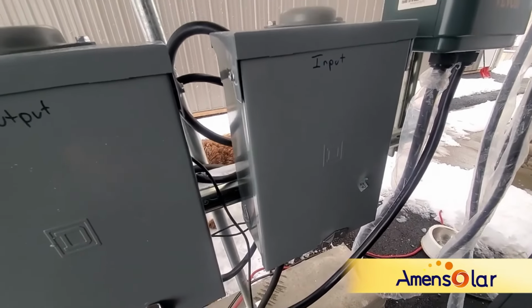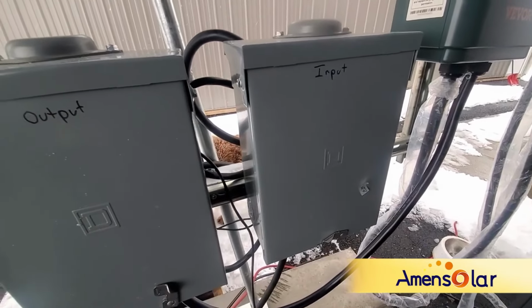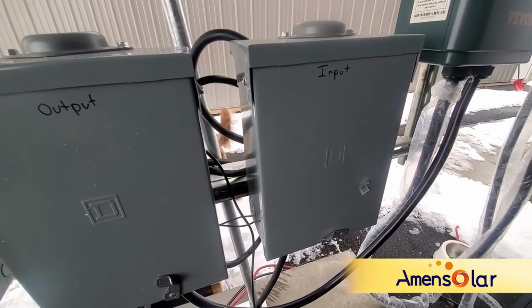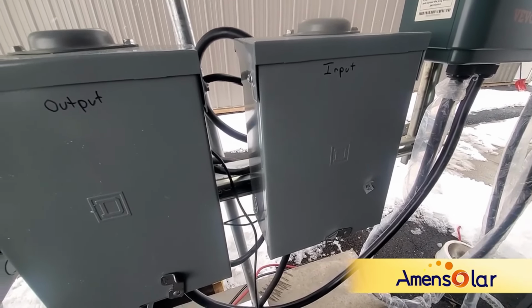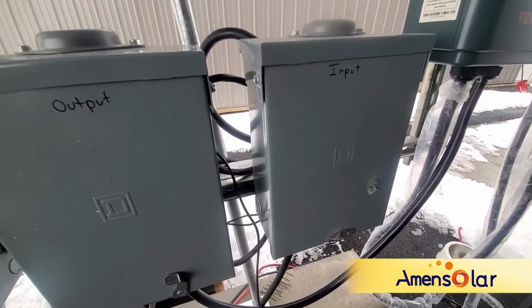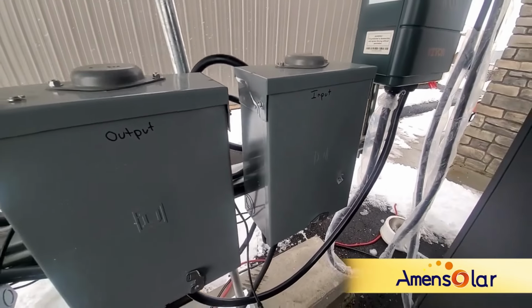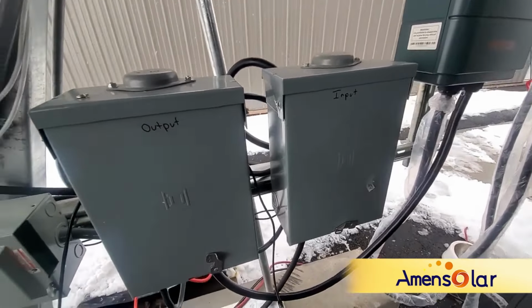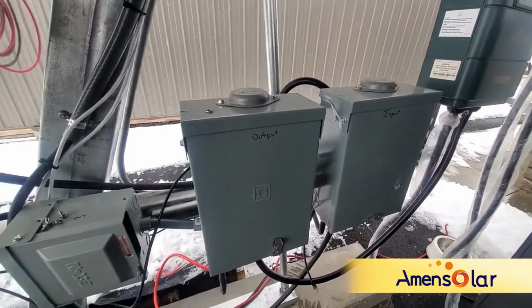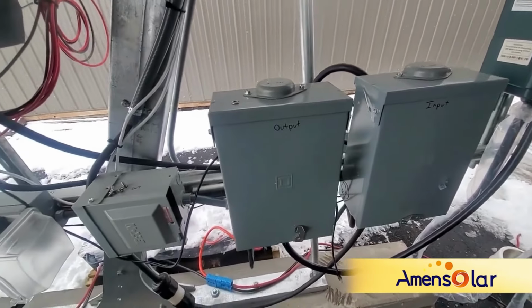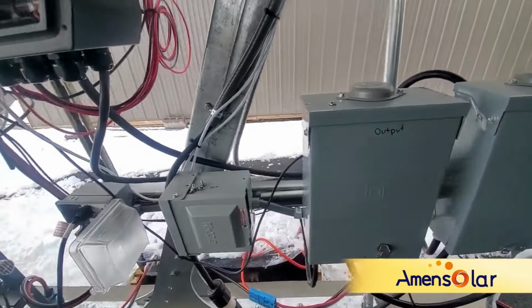The arrow always points to the source of the power. So if it was generator, the arrow points towards generator. If it's utility, the arrow points to utility. And I've noticed on the forum a few people have got that wrong on other model inverters, wondering why it's not zero exporting, because the CTs were installed the wrong way around.